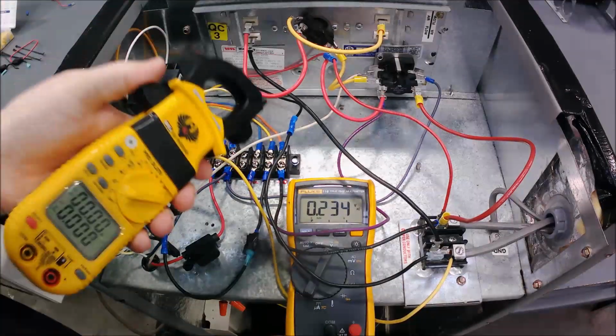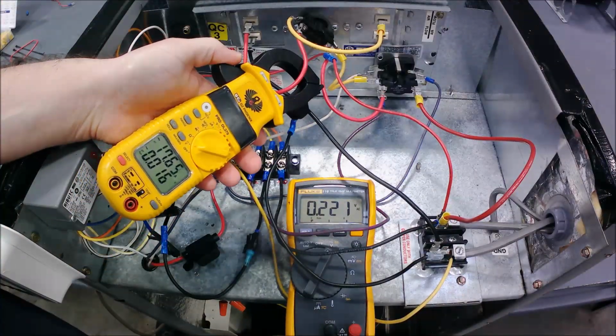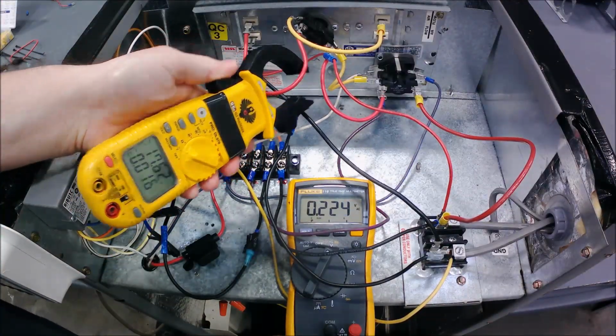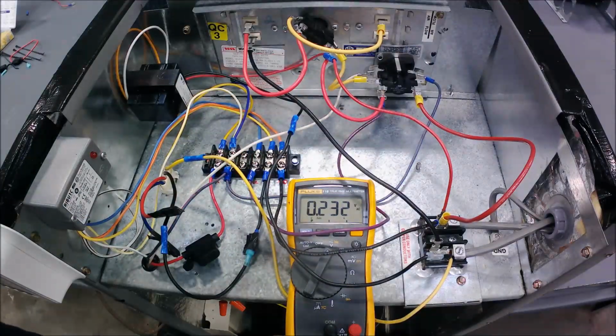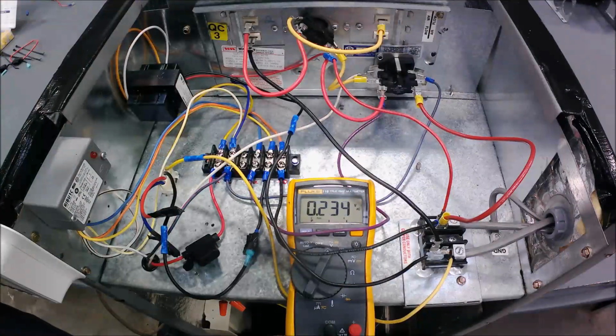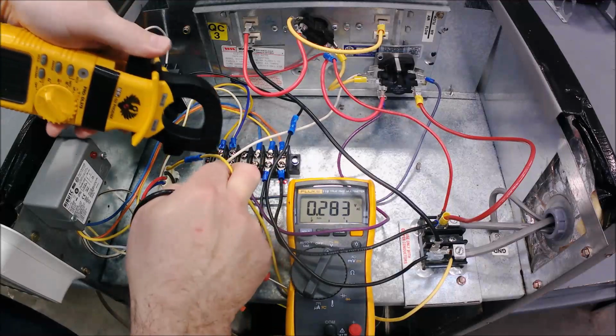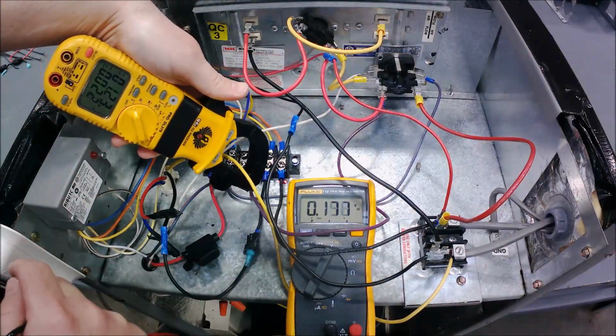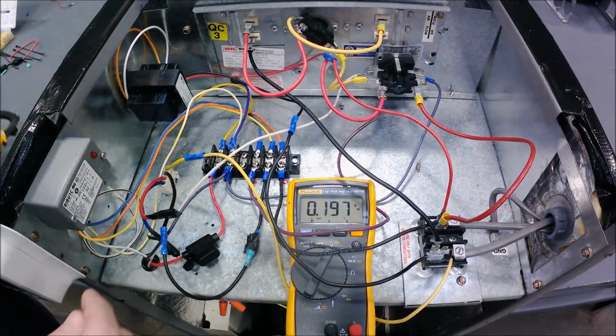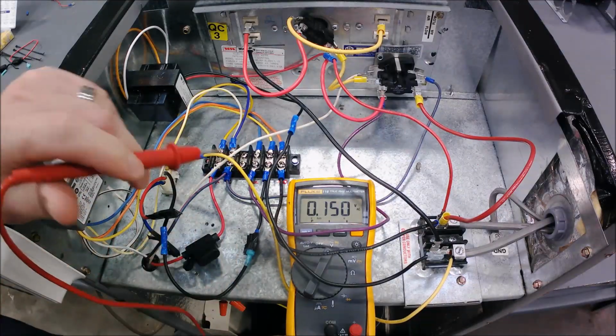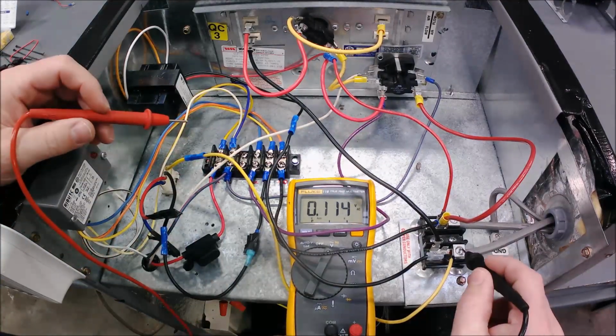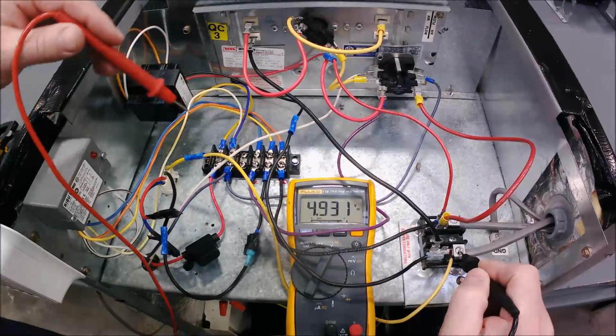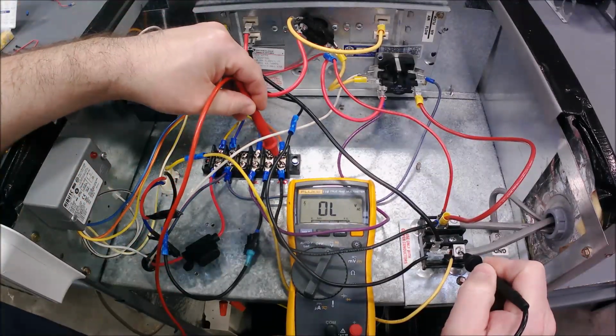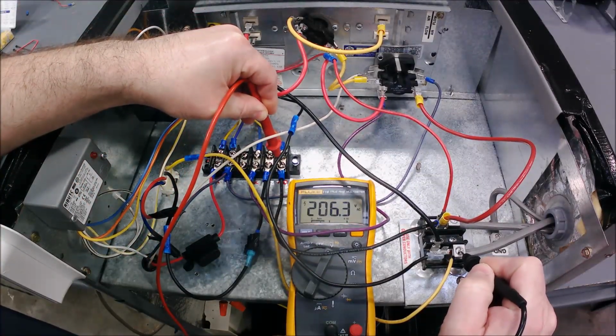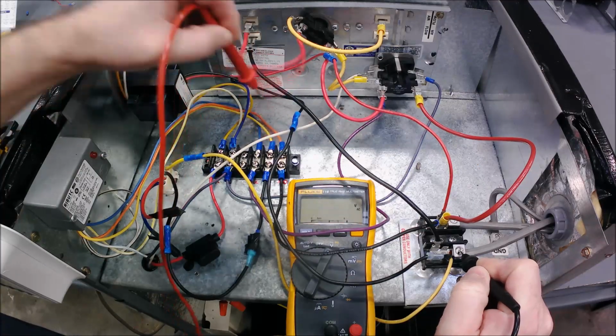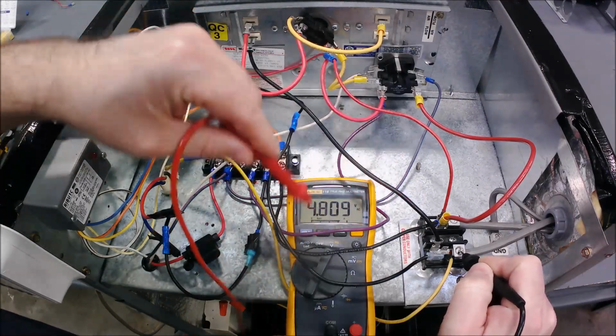So if I check my heater, I've got 17.6 amps. For my fan, there's the yellow right there, I'm going to have 1.23. So as far as function, we wired it in right. And now if I go on my L2 terminal block and I check here, I've got 208, but only because it's already plugged into the terminal.